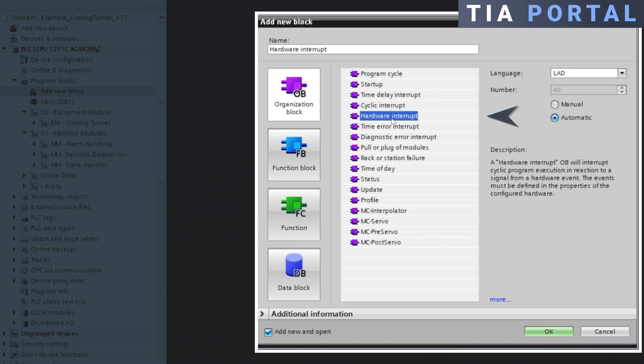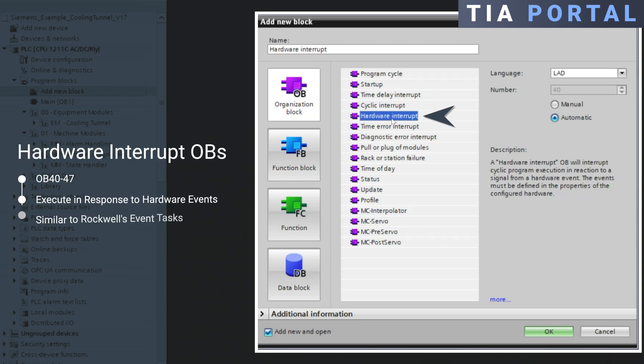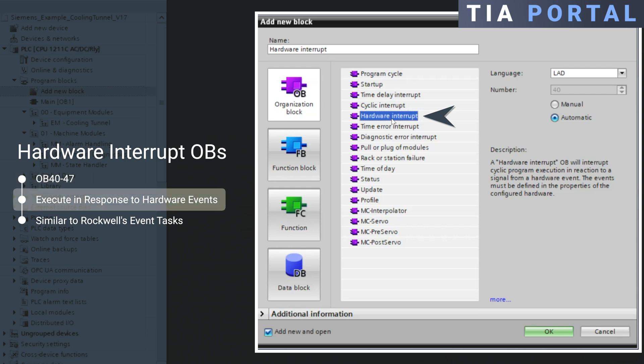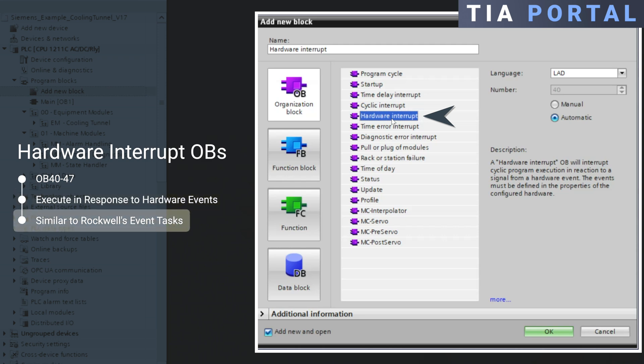Next up, hardware interrupt OBs, ranging from OB40 to OB47, are OBs that execute in response to hardware events, similar to an event task in Rockwell. For instance, if a module detects an error, or a sensor signals a condition, the associated OB executes.